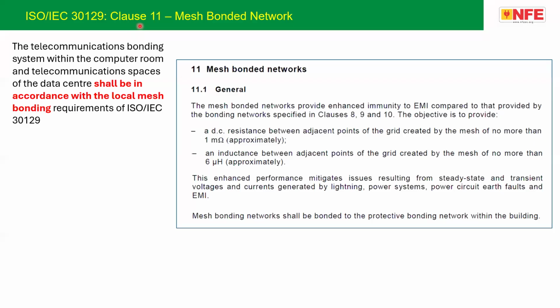For example, clause 11 of the standard 30129 says mesh bonded network. The mesh bonded network provides enhanced immunity to EMI compared to that provided by the bonding networks specified in clauses 8, 9, and 10. That means whatever is recommended in 11 is better than 8, 9, and 10.